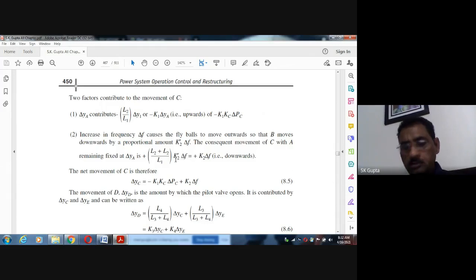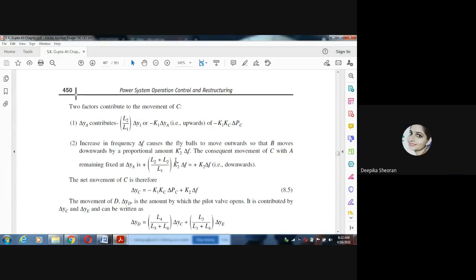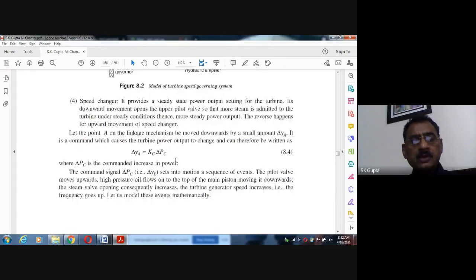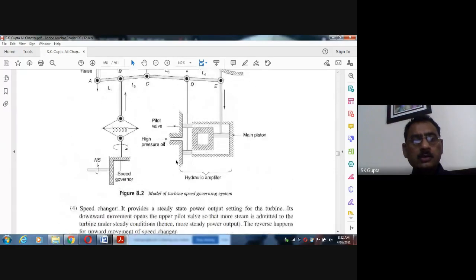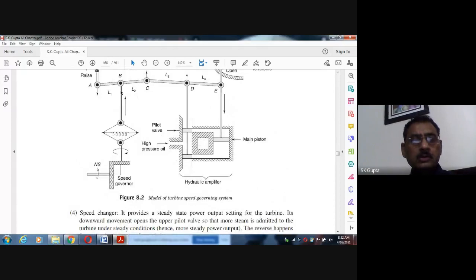This YV इसी लिंकेज मैकेनिज्म। देखिए YV क्या था, ये जो मैं कह रहा हूँ, इसका मूवमेंट YV है। This movement is proportional to the change in frequency. यहाँ अगर फ्रीक्वेंसी मीन्स स्पीड के अकॉर्डिंगली सेंट्रीफ्यूगल फोर्स, they will go up linearly, they will go out, or they will come down, they will come inside, and accordingly this will go up.